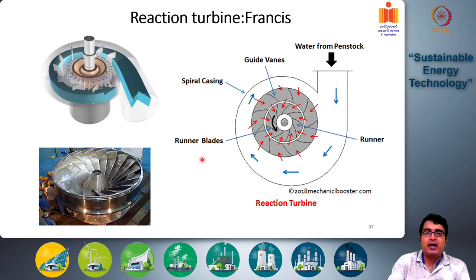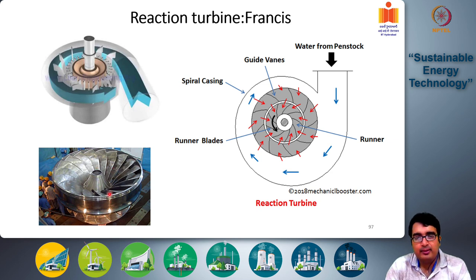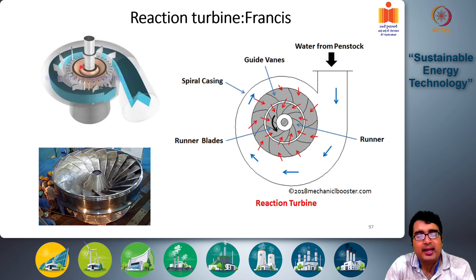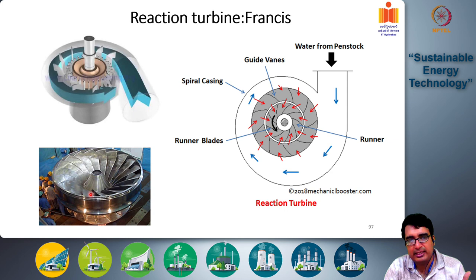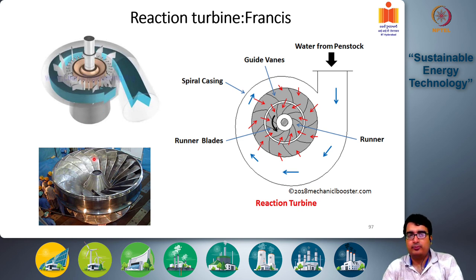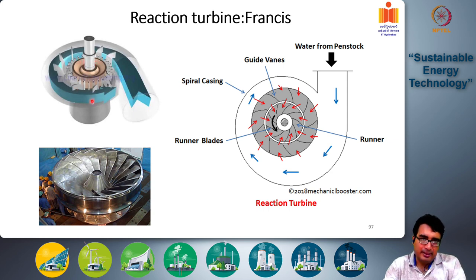This is an example of a Francis turbine — the internal rotor blades are shown here with the shaft visible. You can see how this system works: water flows through the penstock pipe, and then you have two blade structures. The stators are connected to the outer frame of the turbine and direct the flow into the rotor blade system. The water comes in, gets directed by the stators into the rotor blades, transfers its momentum, and then exits at the bottom.